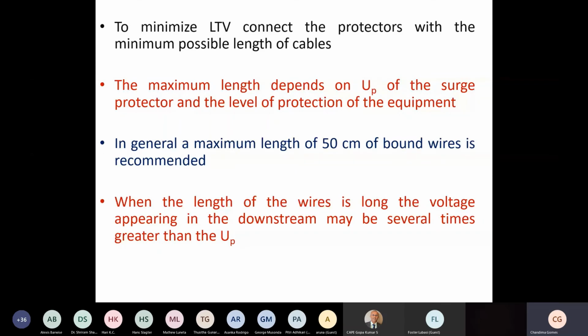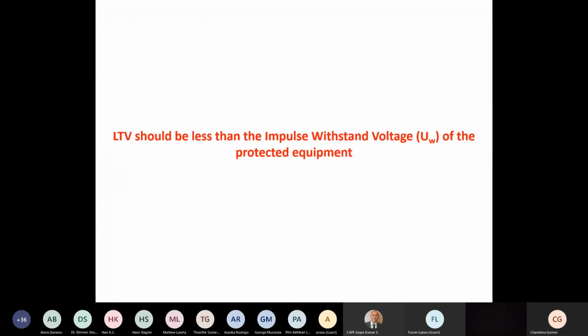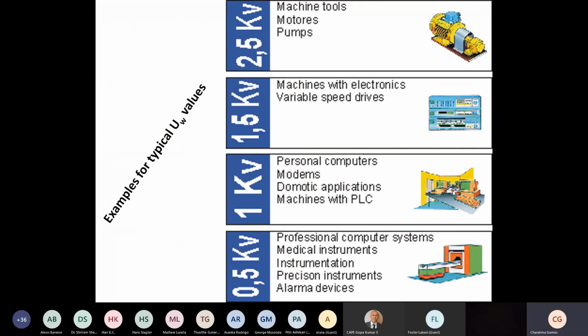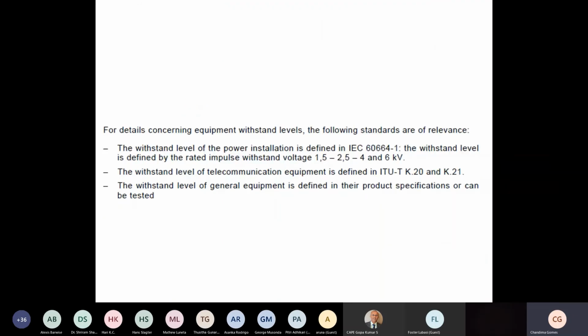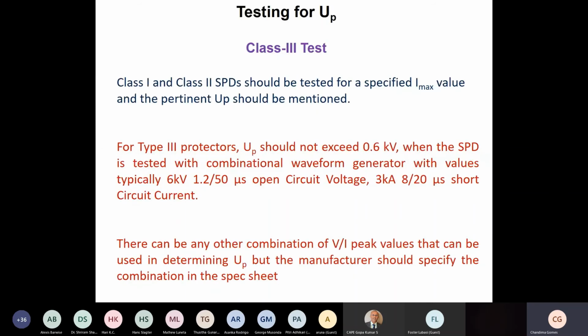Actually, the new standards are giving another equation for that. I'm not going into that due to the time restriction. Better stick to 50 centimeters maximum length between the line and the SPD and earth. So these are some values of impulse withstand voltages. These are some standards which give the impulse withstand voltage of equipment.